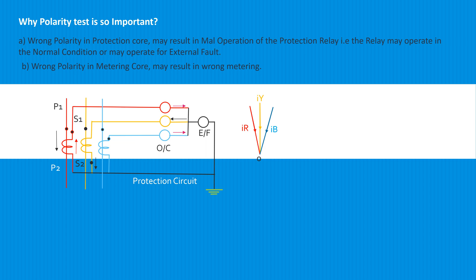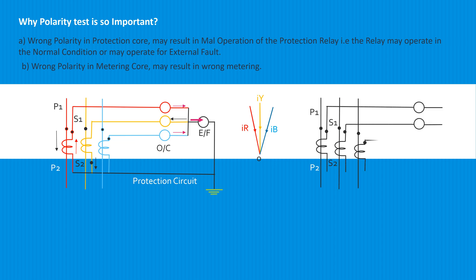No current flows through the earth fault relay. But when any of the CT currents is reversed due to a change in polarity, this balance is broken and current flows through the relay, causing the relay to operate in normal condition. If CT polarity is reversed, the metering would show energy flowing in the wrong direction.